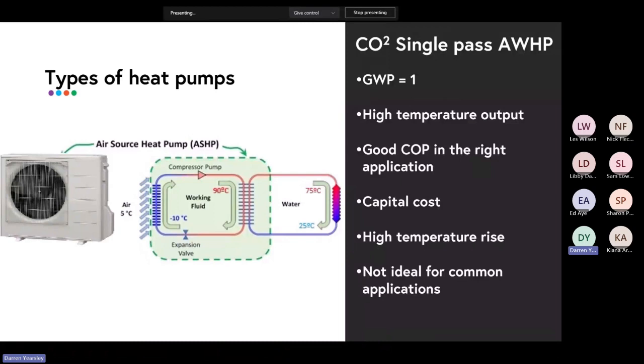Okay, so the limitation of that is you can now no longer create a clean model about what the efficiency of the heat pump will be in this application, because it is totally tied to the duty cycle of the building. So if the building is under light load and you don't have unlimited supply of cold water to run through the appliance, and 70% of your energy is in recovering the tanks rather than during draw off, the COP of the system would be quite different.